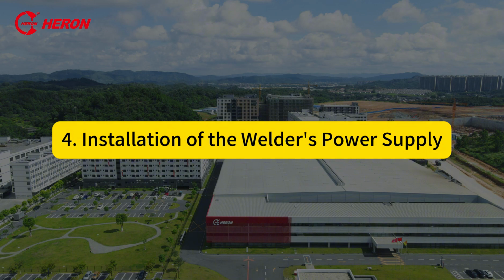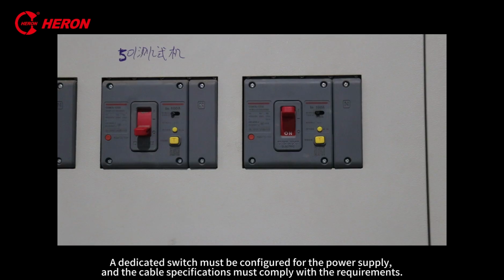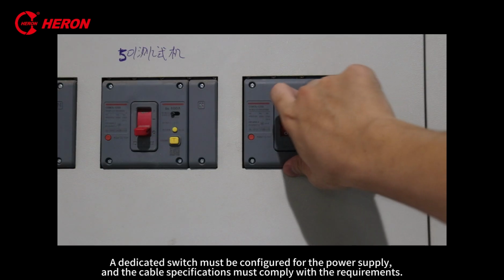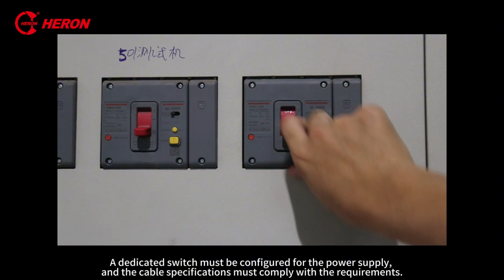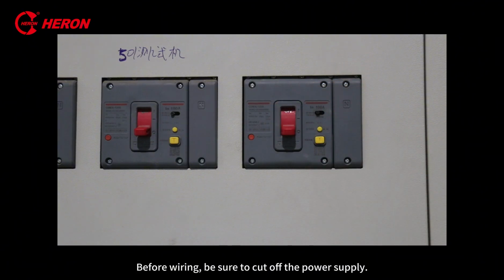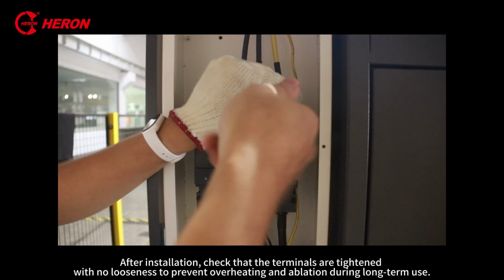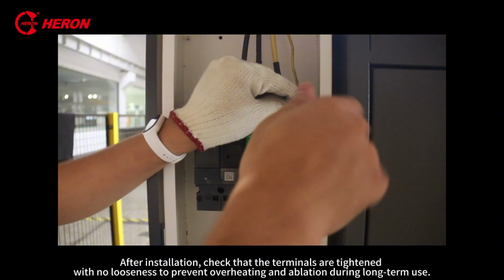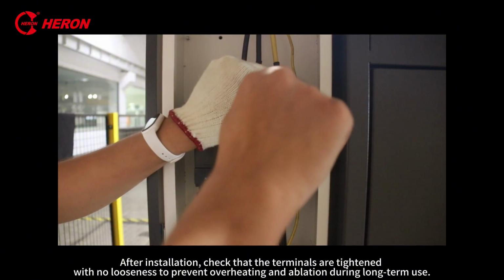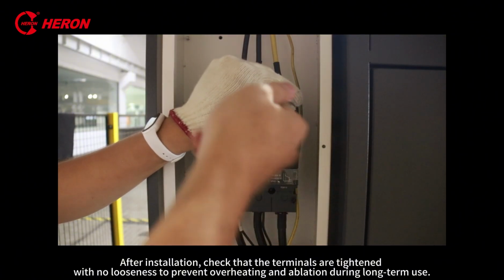4. Installation of the welder's power supply. A dedicated switch must be configured for the power supply, and the cable specifications must comply with the requirements. Before wiring, be sure to cut off the power supply. After installation, check that the terminals are tightened, with no looseness, to prevent overheating and ablation during long-term use.